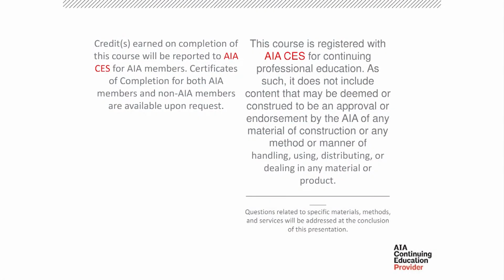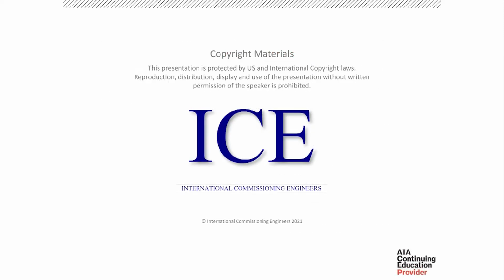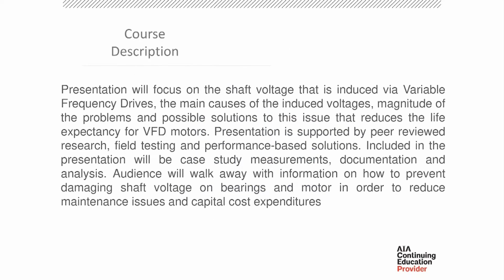The standard AIA message to make sure that we're doing everything in compliance with continuing education. And of course, the copyrighted material by our company, International Commissioning Engineers, better known as ICE. This course description presentation will focus on the shaft voltage that is induced from a variable frequency drive, the main causes of the induced voltages, the magnitude of the problems, and possible solutions for this issue that reduces life expectancy for VFD motors. The presentation is supported by peer-reviewed research, field testing, and performance-based solutions.